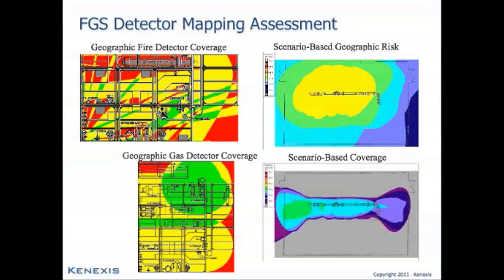Ultimately, the fire and gas mapping output should look like the figures shown on this slide. In the top left corner, you can see geographic fire detector coverage. In this specific output, areas that are shown in green are covered by 2 or more detectors. Areas that are covered in yellow are only detected by a single detector, and areas that are shown in red are seen by no detectors. So there is no coverage at that location in the elevation of interest. Other items that you might want to note are areas that are grayed out would be areas where there is equipment located on the elevation of interest. Thus, that needs to be removed from the calculation of coverage, as it is inside the vessel, thus does not need to be covered inside the vessel or the piece of equipment.